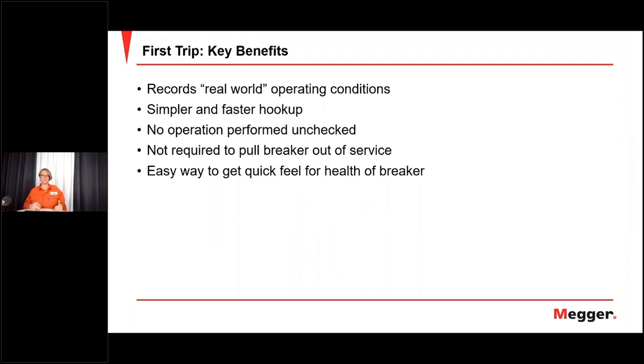So first trip reveals real condition, real world. What's the status of the breaker before you start any grease, any operations? It's as when you come there. And it's quite a simple and fast hookup, so it's quite efficient. And you will have no operation which is not controlled during the measurements. And you don't even have to take the breaker out of service.